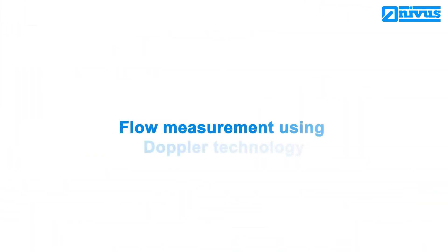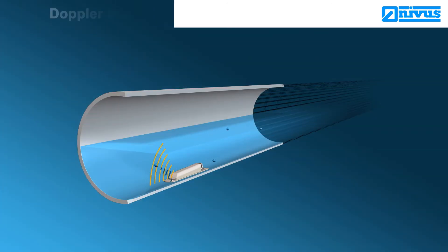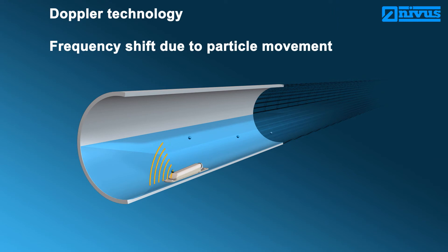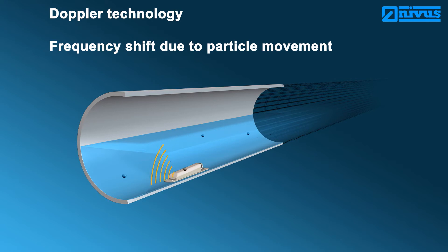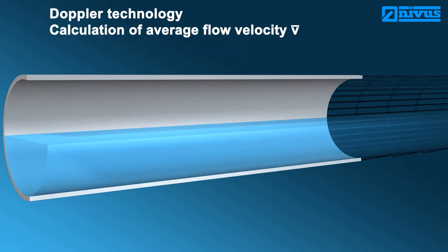Flow measurement using Doppler systems. The Doppler technology uses a sensor continuously transmitting ultrasonic signals at a constant frequency. The particles contained in the medium reflect the signal. The particle movement shifts the frequency of the reflected signal, and the frequency shift is detected by the sensor. The greater the particle velocity, the greater the frequency shift. Doppler measurement is a spot velocity measurement.